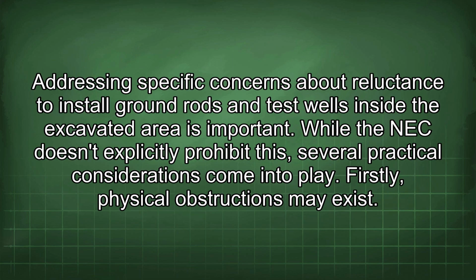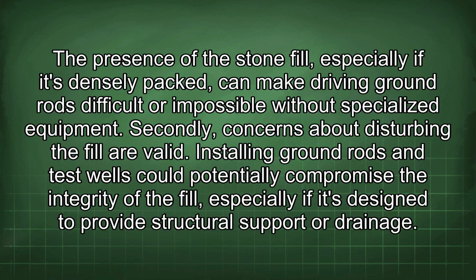Addressing specific concerns about reluctance to install ground rods and test wells inside the excavated area is important. While the NEC doesn't explicitly prohibit this, several practical considerations come into play. Firstly, physical obstructions may exist. The presence of the stone fill, especially if it's densely packed, can make driving ground rods difficult or impossible without specialized equipment. Secondly, concerns about disturbing the fill are valid.